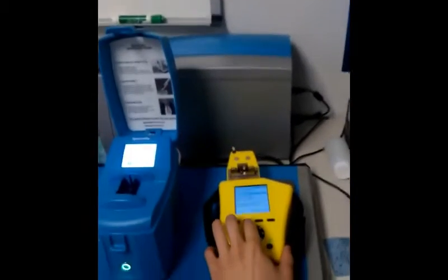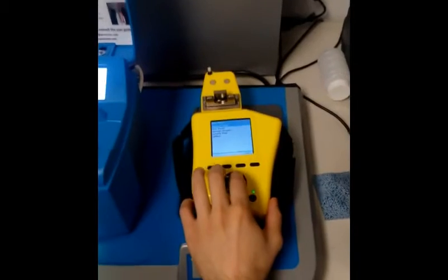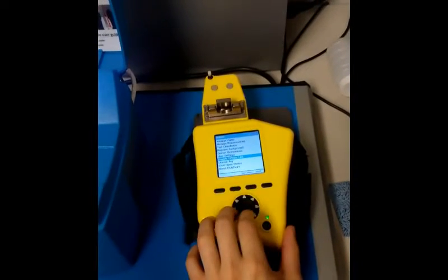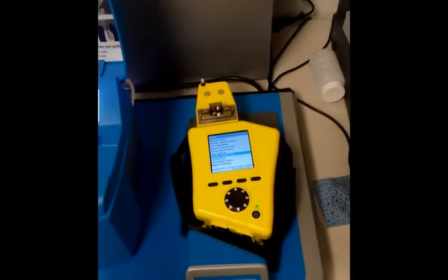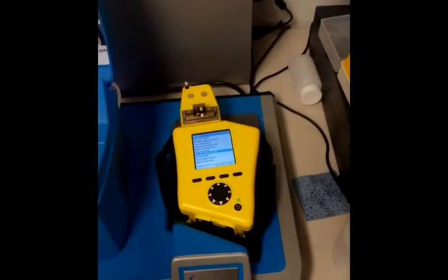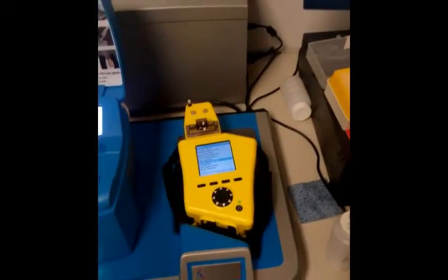Before I go on with that, if we turn our attention to the fluid scan, you'll see that if I go to utilities, there is disable oil view link. You want to make sure that it's enabled. If you turn on your OilView and you're seeing that it is disconnected, this is one of the first and easiest things for you to check. Just make sure that it's enabled. That actually happened with us, and we did enable it. Especially during a fresh installation, that's one of the best things you can do.